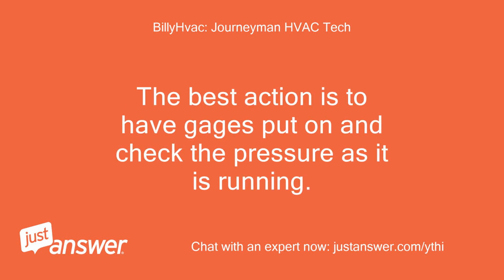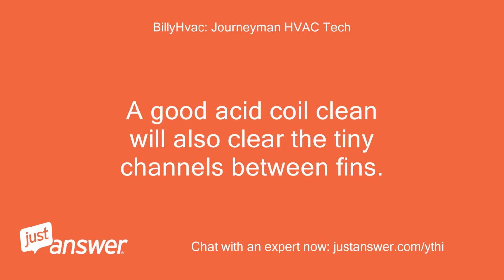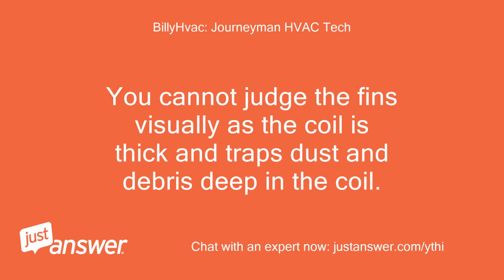The best action is to have gauges put on and check the pressure as it's running. A good acid coil clean will also clear the tiny channels between fins. You cannot judge the fins visually, as the coil is thick and traps dust and debris deep inside.